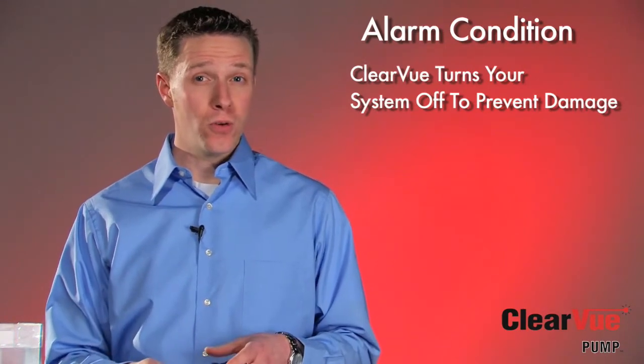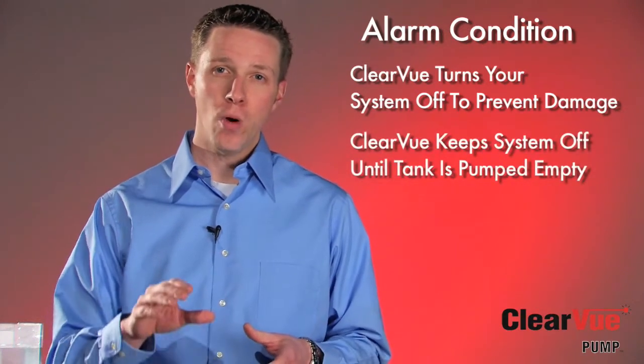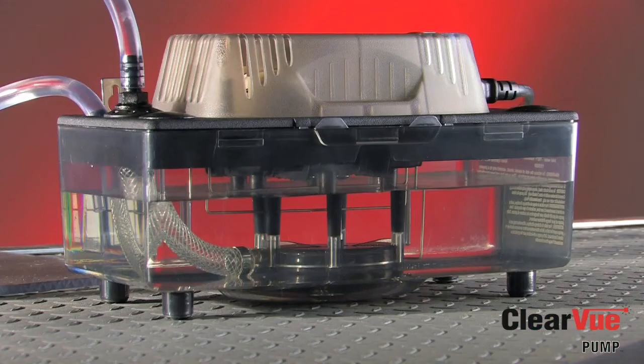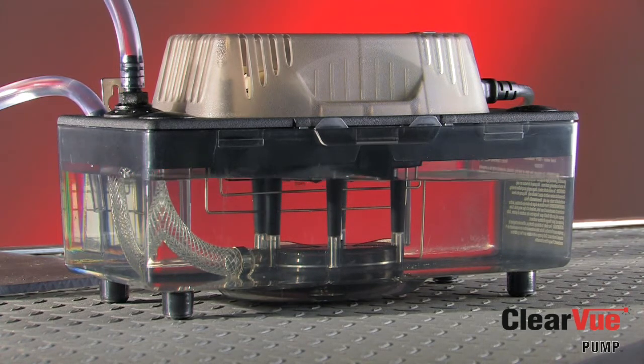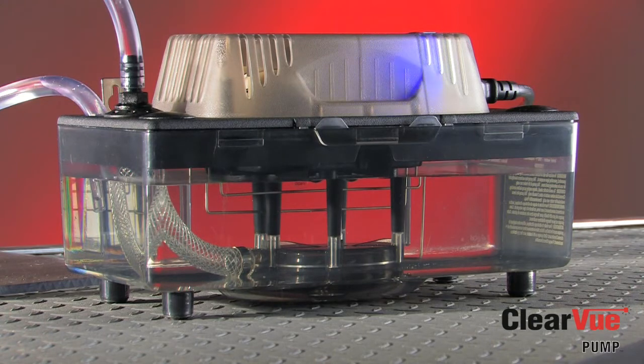The key difference between ClearVue and a normal condensate pump is that it will keep your compressor shut off until water has pumped down to the bottom of the tank and come off of that empty sensor. As you can see, water is sloshing back and forth in the tank during a clog. If your pump has a mechanical float, it will bounce up and down as the water sloshes in the tank, turning that alarm signal off, on, off, on. This will happen in any condensate pump with a mechanical float. This off-on alarm cycle will then short cycle your compressor, which we know can cause damage. Again, no float, no problems.